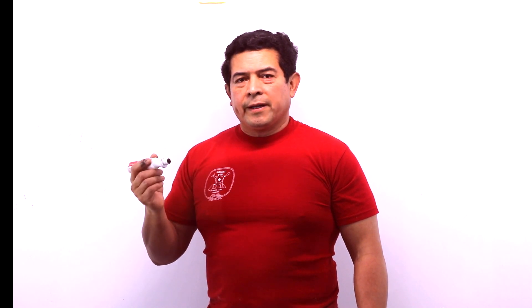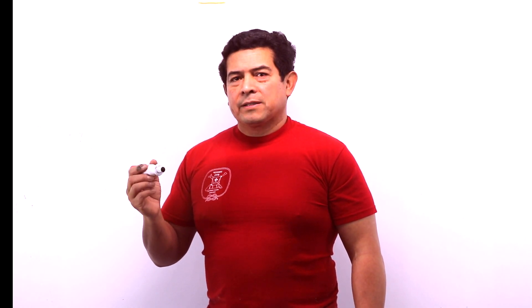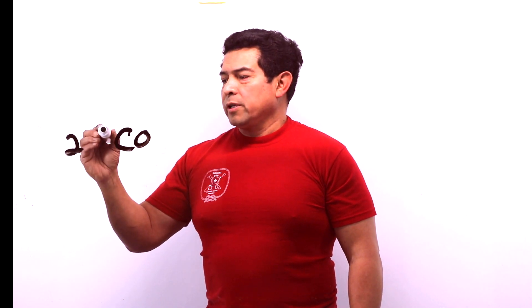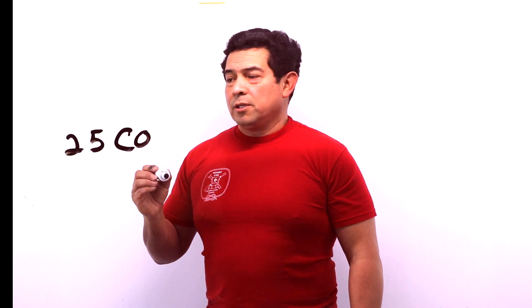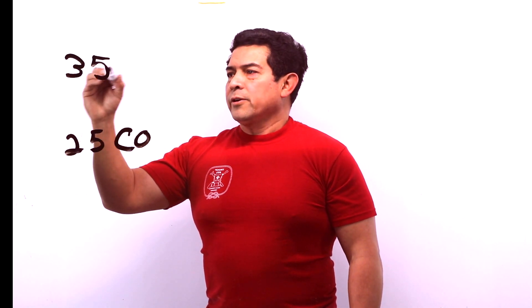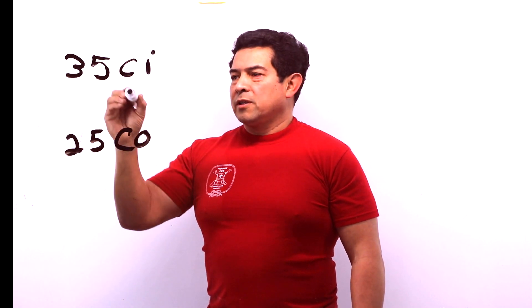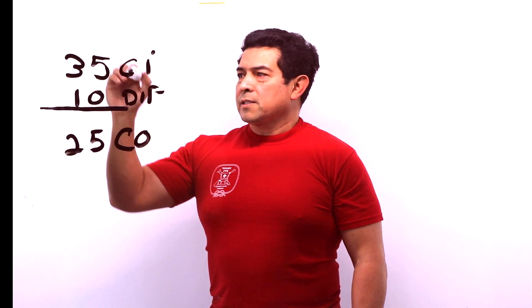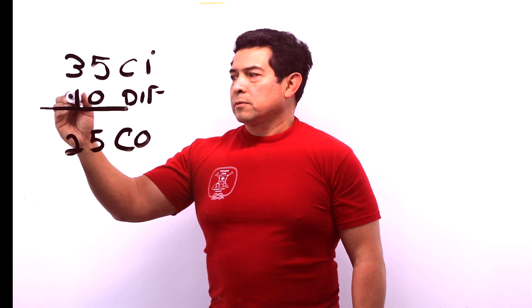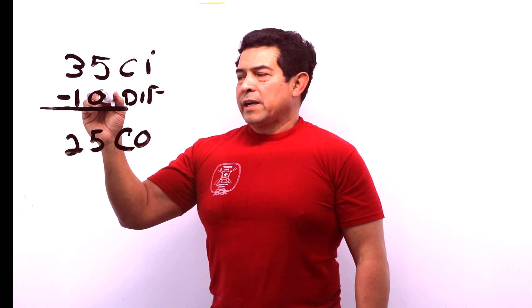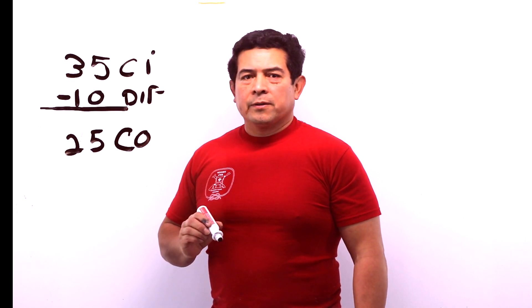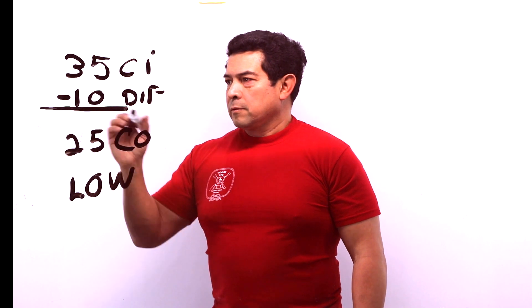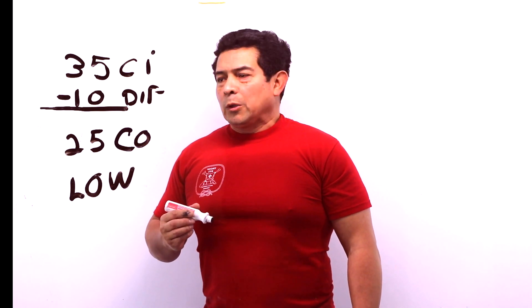Now on a low pressure switch, the cut out is the cut in minus the differential. So we want it to cut out at 25 PSIG. The cut in is going to be 35. The differential is going to be 10. The cut out is the cut in minus the differential. So you take the 35, subtract the 10 for the differential, and the cut out is going to be 25 on the low pressure switch. That's what that means and that's how you would set a low pressure switch.